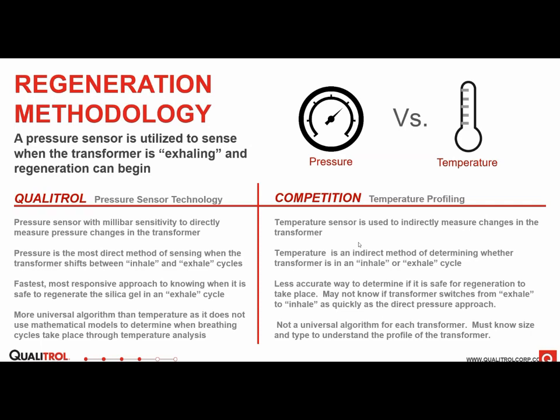On the topic of picking a regeneration time that is best to dry out the silica, where the transformer is exhaling, we use pressure sensor technology. Every 15 minutes, we close the solenoid and sense the pressure, whether it's an inhale or an exhale. And we track where those exhale cycles are. So we'll track the time of day. Say in the morning, the transformer has increasing load, temperature is increasing, and it's breathing out. So it breathes out from maybe 6 a.m. to noon. We're going to be tracking that pressure increase over that time. So we use real data to know when the best time to regenerate is.